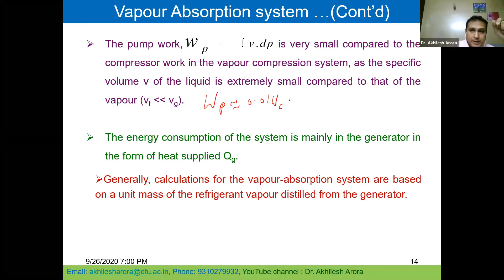If I compare it with a vapor compression system, the pump work is very small, because the specific volume of the liquids is very small. The pump work would be somewhere around 0.01 times that of the compressor work. So it is nearly 100 times less than the compressor work if we use a vapor compression system. Within the same pressure limits, the compressor power will be about 100 times more than the pump work. So it's very small.